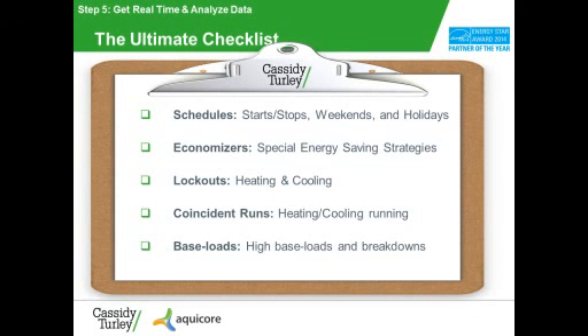Often, if you understand your cooling loads and you understand your mechanical load and what it would look like on your daily load profile, if you have simultaneous heating and cooling going on, it shows up right on your screen. And you can set alerts to say, I know where my top is, I know where my max load is. If my chiller is running at 100% and my building's fully occupied, if I go beyond that, I must be using electric heat.